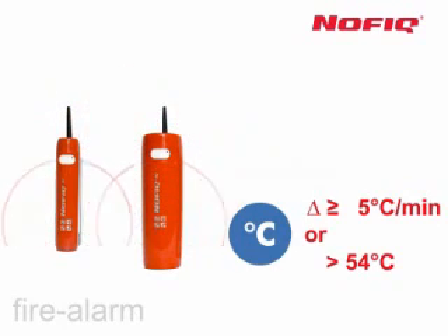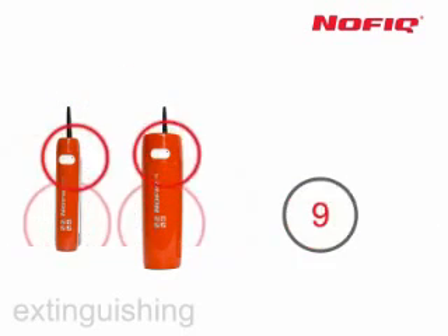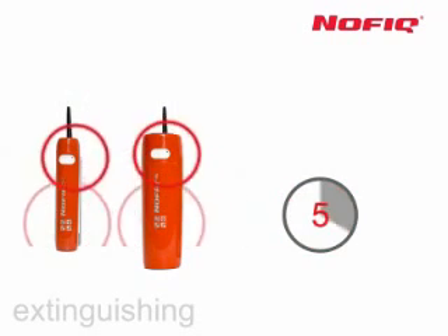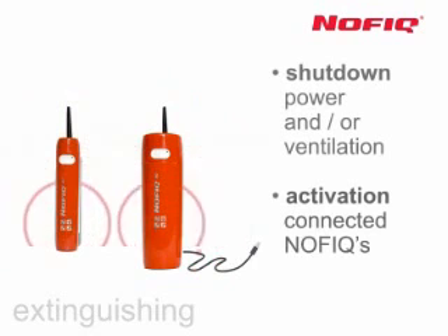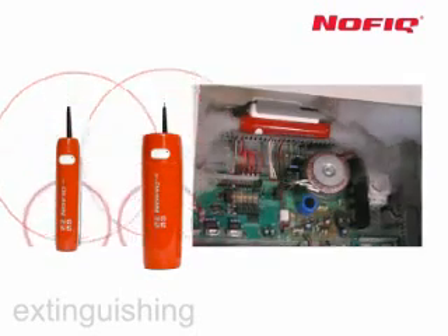In the event of a fire alarm, the NOFIQ system has a built-in 10-second delay before it initiates the fire extinguisher. During that delay, you can take any required action via the NOFIQ 20 or NOFIQ 80 — for instance, you could turn off the ventilation system or disconnect the switchbox from the power supply. The NOFIQ uses an aerosol extinguisher, an extinguishing agent with very distinct advantages.